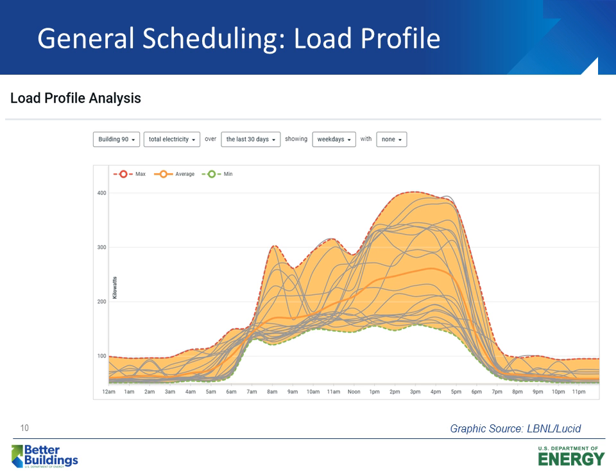Another very common thing to look at is load profiles. This is from LBNL, the building we're in, Building 90, and you can see the load shape. This shows the last 30 days, each gray line is a day, and we have min, max, and average. There are definitely things you can see in this, and it's nice to have a summary plot. You can look at weekdays, weekends, and holidays to try to identify scheduling issues and baseload issues, and so forth. So load profile is very common.